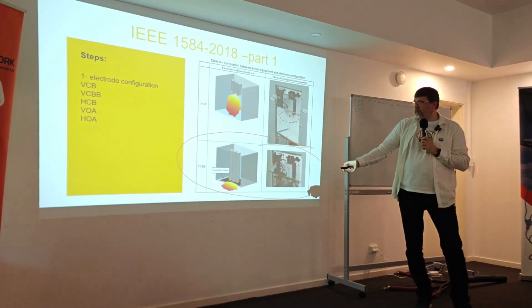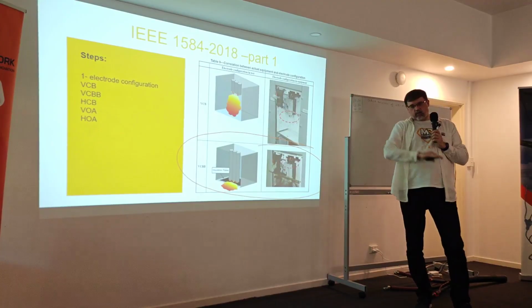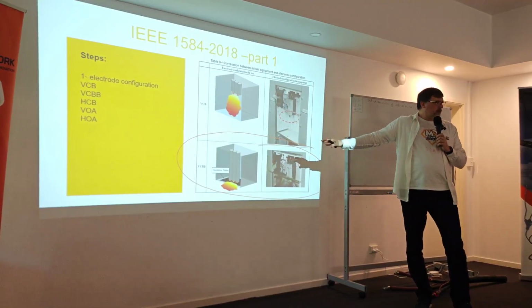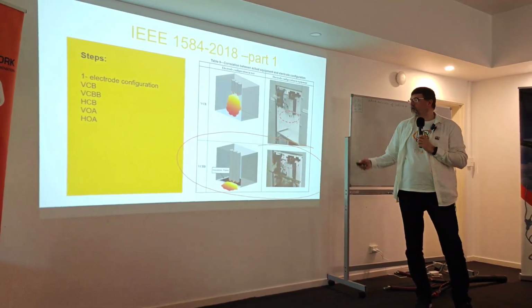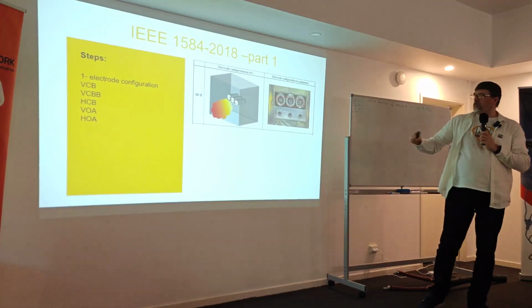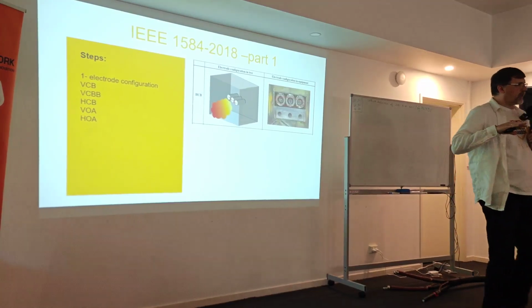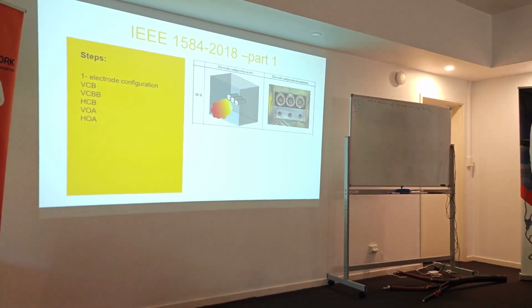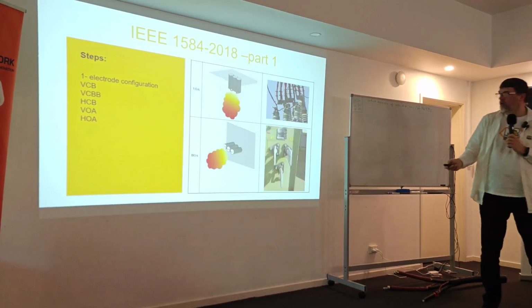We choose the VCBB because on the panel there were also covers on the top and bottom. VCBB for a moment, just to make it easier for you. Sometimes they are like HCB, and HCB is the worst case most of the time, when the electrodes are towards you, like this. This is the worst case situation for the arc flash calculation, because it will be extended or concentrated towards you, especially when there is an enclosure behind it.